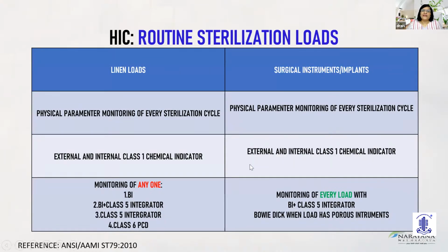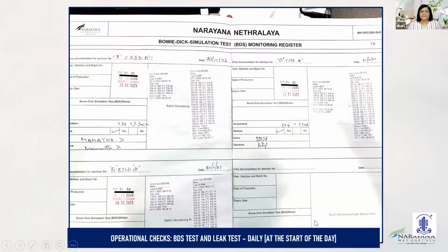Now coming to the routine sterilization loads. In linen loads, we have to remember that physical parameter monitoring of every sterilization cycle is important. You can have an external and internal class 1 chemical indicator for this, and monitoring of any one is okay, like a BI or a BI with class 5 indicator, or a class 5 indicator alone, or a class 6 PCD can be done. When you have surgical instruments or implants, then the physical parameter monitoring of every sterilization cycle is of course important. Then the external and internal class 1 chemical indicator can be used, but monitoring of every load with BI with class 5 indicator or a Bowie-Dick when the load has porous instruments should be done.